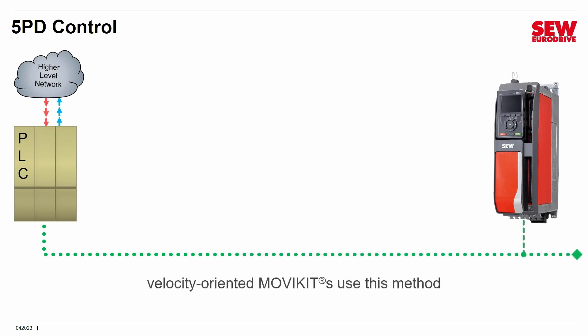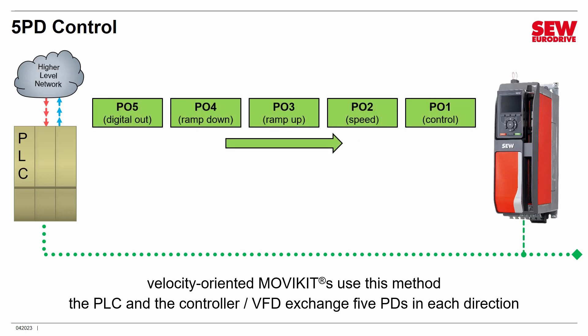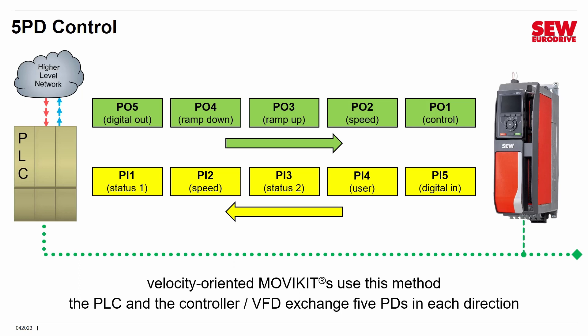SEW describes field bus control by how many process data words the PLC exchanges with VFDs. A very common type is called 5PD, using five process data words — velocity-oriented MOVIKITs use this method. PO1 carries control information, PO2 sends the speed value, PO3 and PO4 are ramp up and down, and PO5 controls digital outputs. The VFD sends back status in PI1 and PI3, current speed in PI2, a user-selected parameter in PI4, and digital input status in PI5.